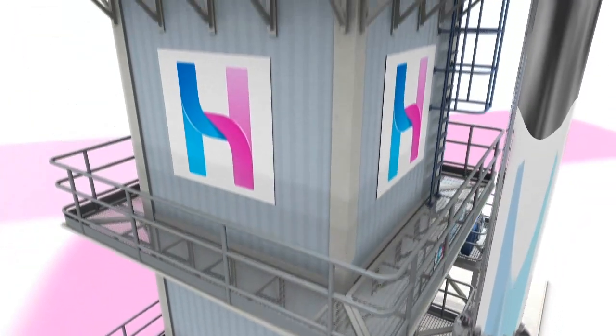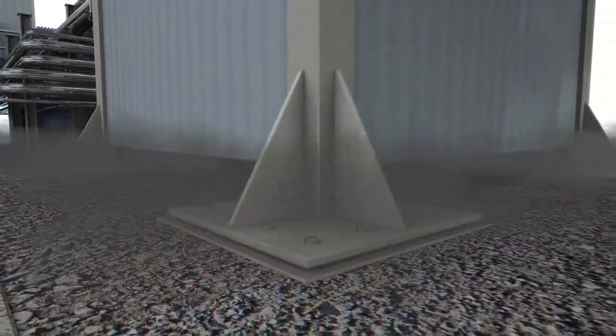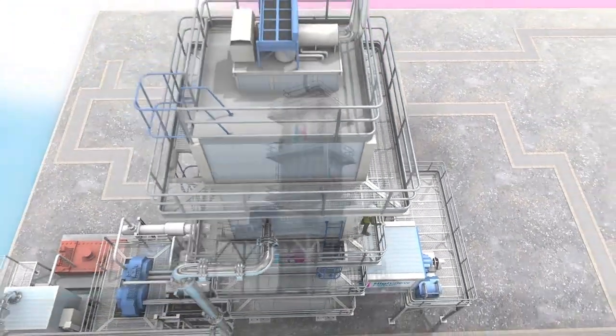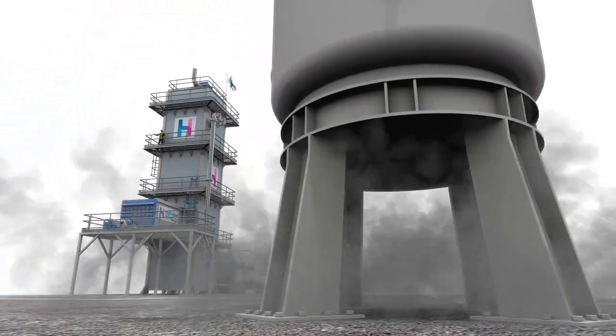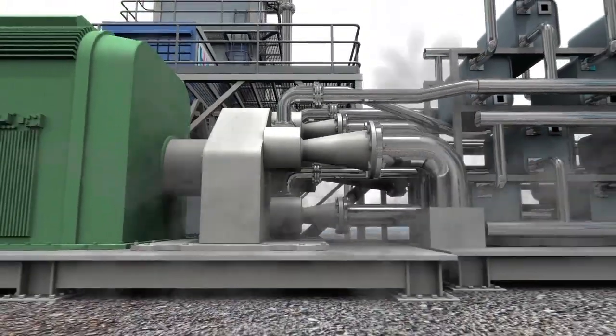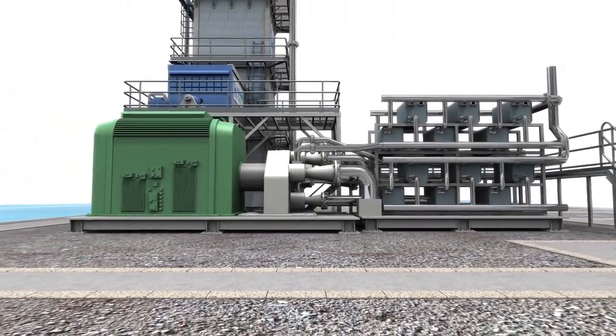Highview's cryogenic energy storage system consists of three main components: a charging device which uses off-peak or excess electricity to power an industrial liquefier which produces liquid air; an energy store where liquid air is held in an insulated tank at low pressure; and the power recovery unit where gasified liquid air is used to drive a turbine and generate electricity.